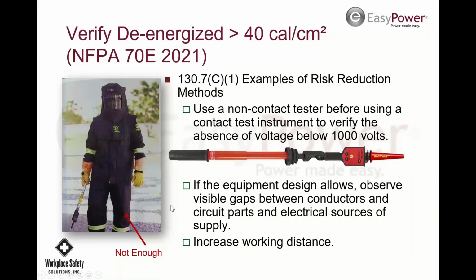This is new in 2021. So this is what they're saying. If you have something greater than 40 calories and you shut it down and lock it out, you still have to verify it's off. So you'll test it at a distance. I've been practicing this for at least 10 or 15 years, and encouraging this kind of test. This is done in addition to a dead live contact test, phase to ground, phase to phase test.